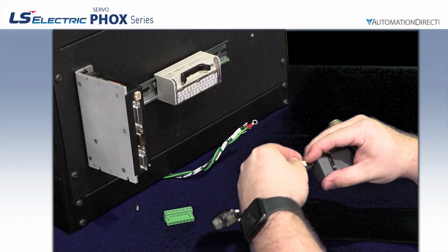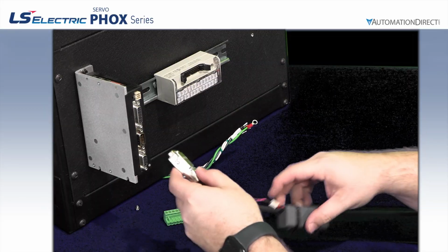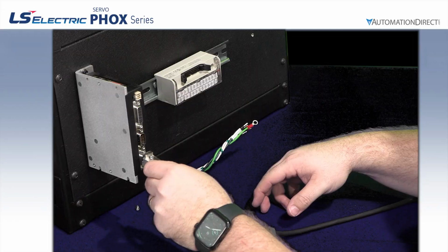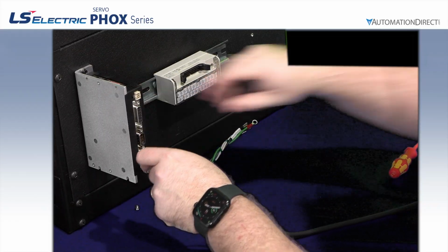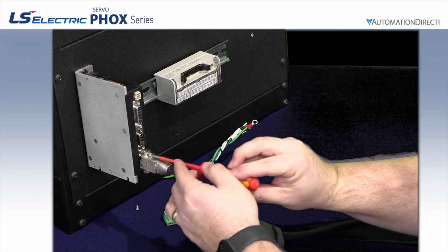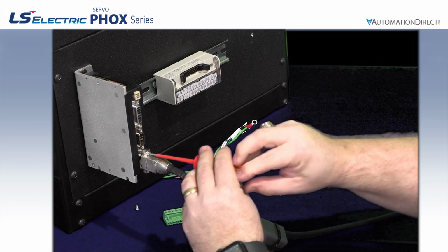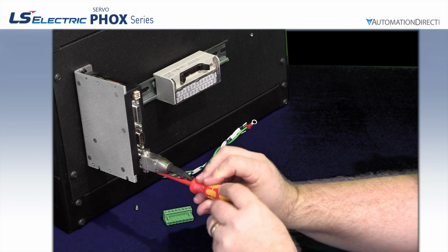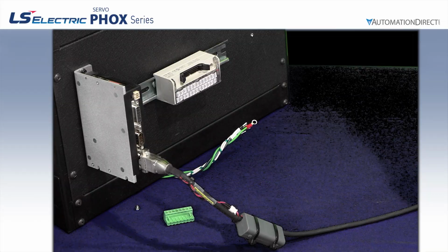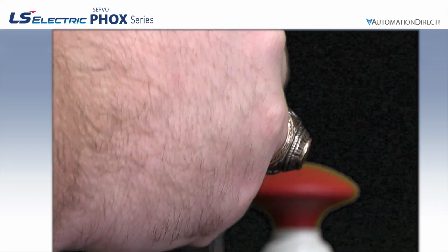For the drive side connections, we will start with the encoder since it's pretty straightforward. Plug the 2 small battery connectors together on the cable so the system can support absolute mode if needed. Then connect the encoder cable to the drive connector labeled Encoder A. Once seated, tighten the 2 screws to secure it. While the system is fully functional with the motor encoder alone, the drive also offers the Encoder B connection. This is only necessary if you need a secondary encoder for closing the position loop on the drivetrain nearer to the load.